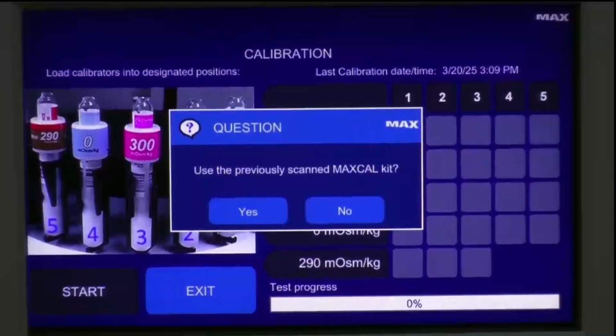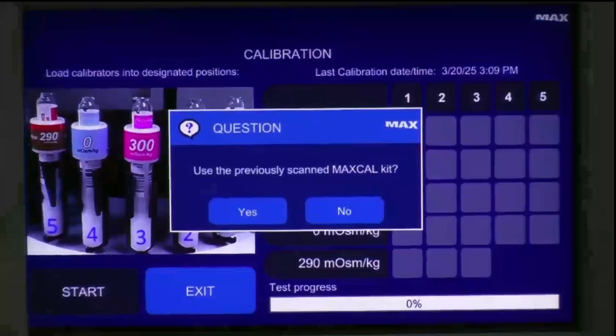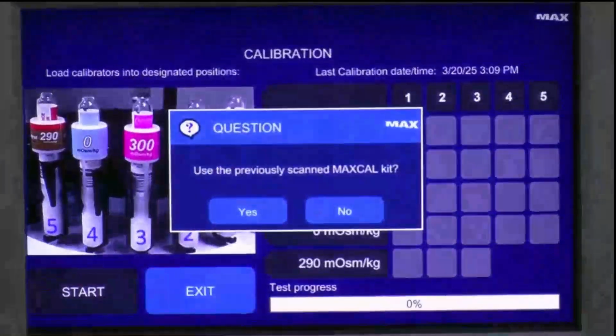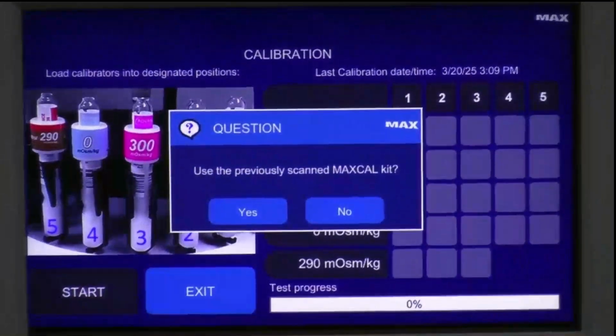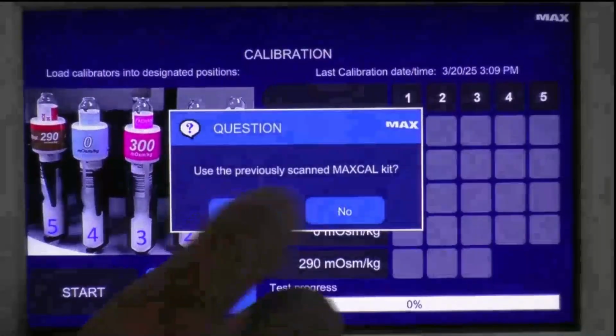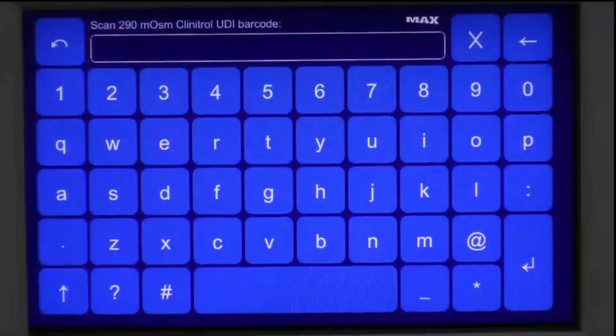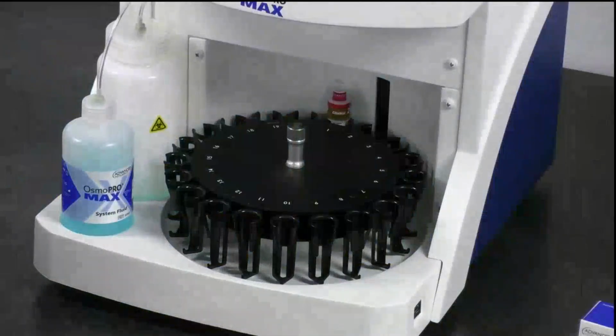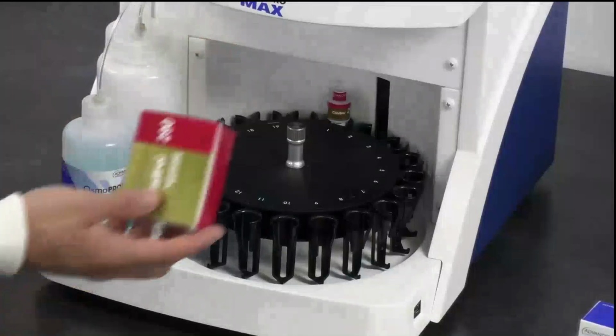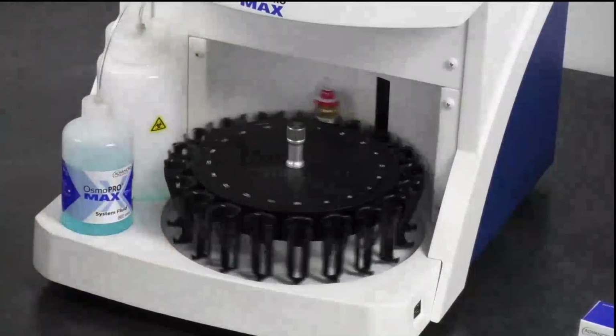So I've already scanned one of the kits in before. Each time you scan into this menu, it's going to ask you to scan the UDI barcode on the side of your OsmoPRO MAX calibrator kit. Remember this kit that I showed you earlier. And then it's going to take you through some instructions on how to set up your calibration. So I'm just going to say yes. And then on the end of every calibration, it's going to ask you to run Clinitrol 290. So you can see how this works, using the scanner underneath the top cover here, I'll scan in my Clinitrol 290.